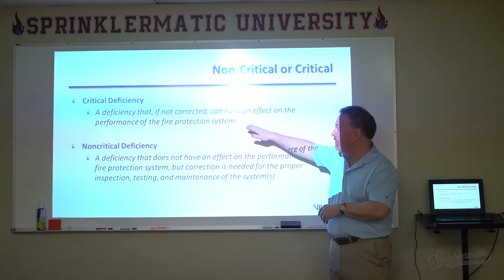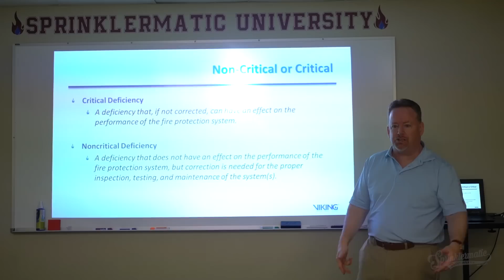It's all about whether, if not corrected, it can have an effect on the performance of the fire protection system. That's a critical deficiency. Here's a non-critical deficiency: it has to be corrected, but it doesn't have an effect on the overall operation of the system. Well, let's go back to my sprinkler up in the ceiling with schmutz on it. If that thing doesn't operate, is it going to have an impact? Yeah, but it doesn't have that much, so maybe it will operate. We're not sure.